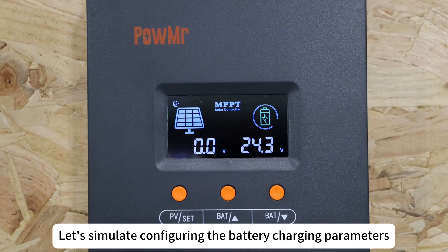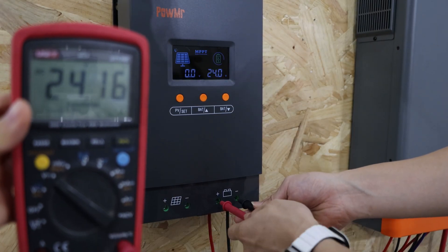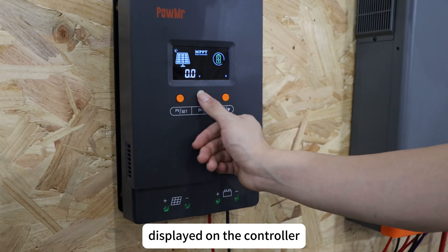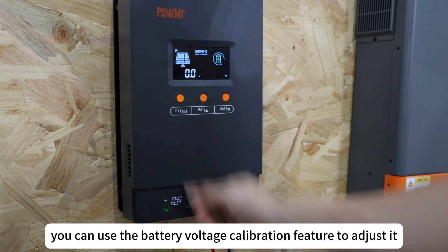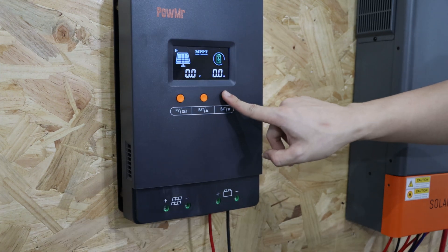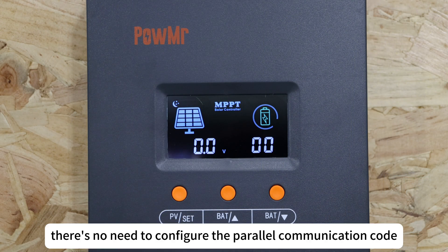Let's simulate configuring the battery charging parameters for a single controller. First, measure the battery voltage using a multimeter. If the detected battery voltage differs from the voltage displayed on the controller, you can use the battery voltage calibration feature to adjust it. In single controller operation, there is no need to configure the parallel communication code.